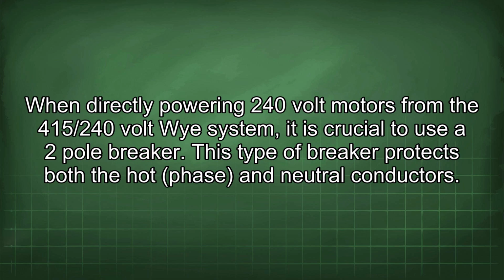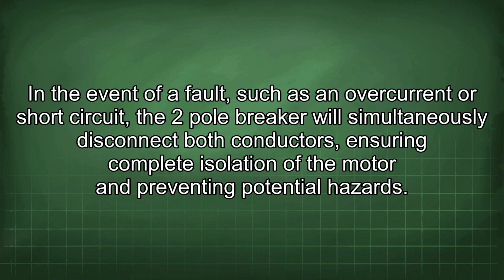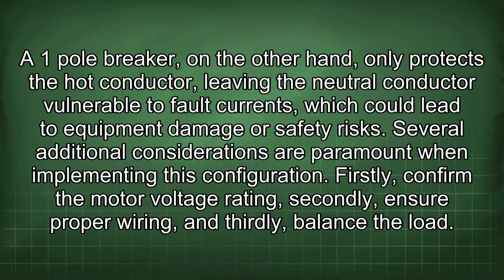When directly powering 240-volt motors from the 415/240-volt Y system, it is crucial to use a 2-pole breaker. This type of breaker protects both the hot phase and neutral conductors. In the event of a fault, such as an overcurrent or short circuit, the 2-pole breaker will simultaneously disconnect both conductors, ensuring complete isolation of the motor and preventing potential hazards. A 1-pole breaker, on the other hand, only protects the hot conductor, leaving the neutral conductor vulnerable to fault currents, which could lead to equipment damage or safety risks.